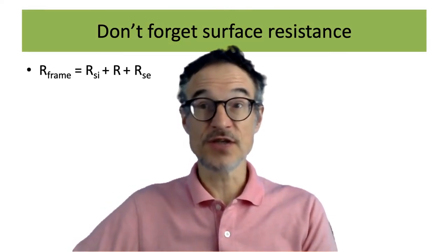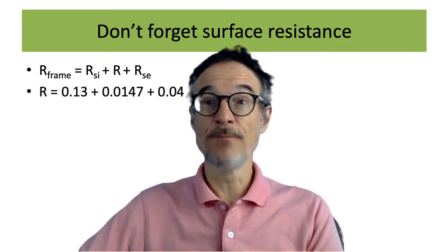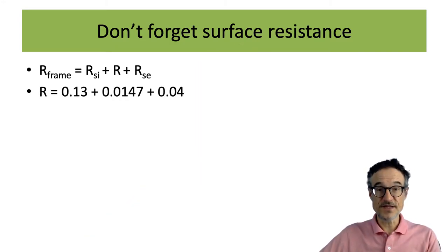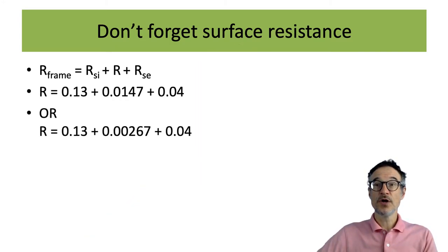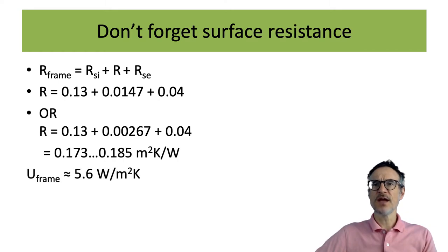Now, the surface resistance is going to be much, much bigger. But whichever of these numbers we choose, it's basically surface resistance is the only thing that's stopping heat around the frames. So that's something like 5.6 for the U value of the frame.